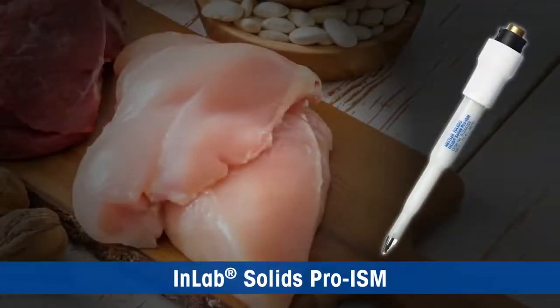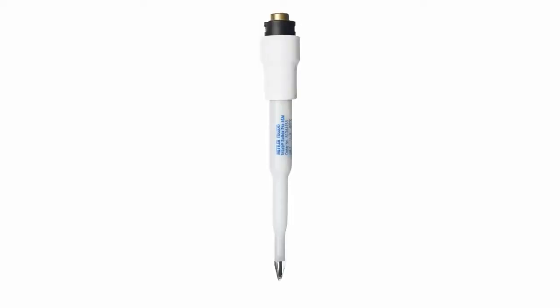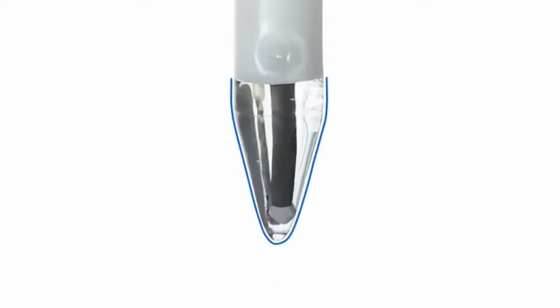Mettler Toledo's solution to these challenges is a specialist sensor, InLab Solids Pro ISM, which is easy to use, maintenance-free, and delivers desirable performance. This electrode has a spear-shaped tip made of thick, toughened glass that allows direct insertion into the solid meat samples. This spear-shaped pH-sensitive membrane is made of LoT glass, which has a low resistance, which helps in faster results. The electrode has an open junction, which avoids clogging and is easy to clean.